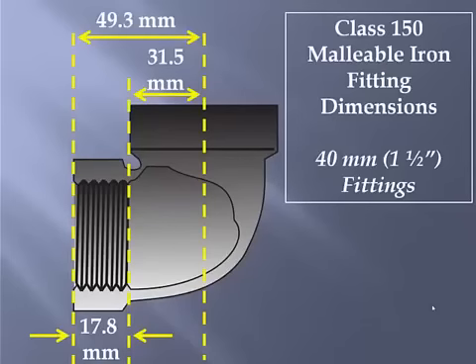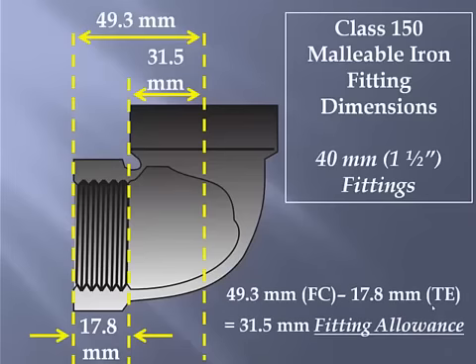So let's take a look at the math on that. 49.3 millimeters, which was the face-to-center measurement, minus the 17.8 thread engagement dimension, resulted in a 31.5 millimeter fitting allowance.